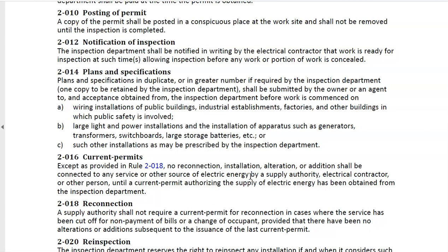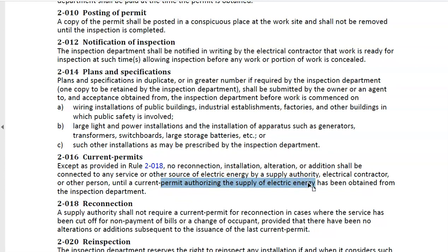There has to be a current permit. A current permit is a pass that comes from the inspection department: we apply for a permit, ask them to inspect, notify them we're ready, they do the inspection, and then they issue the current permit which authorizes the supply of electric energy. We submit that to BC Hydro and then BC Hydro can connect power. Until that has happened, no reconnection, installation, alteration, or addition shall be connected to any service or source of electric energy. You are not allowed to build an installation and run it off a generator, because that is considered a source of electric energy — it still needs to be an inspected installation.